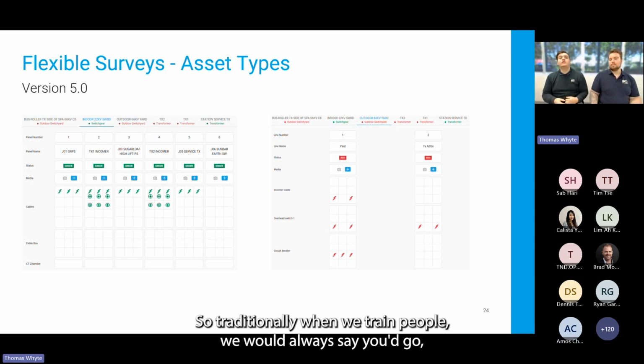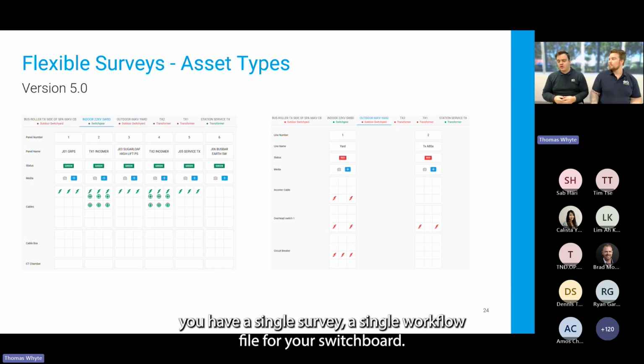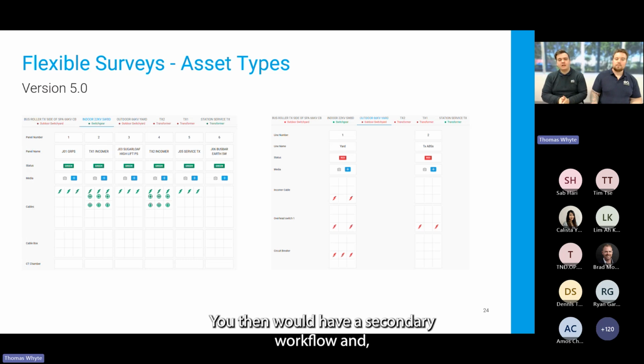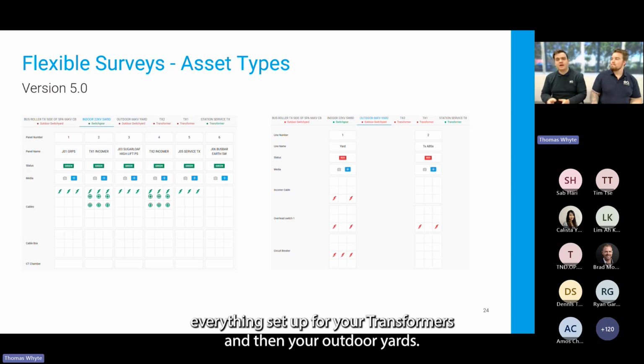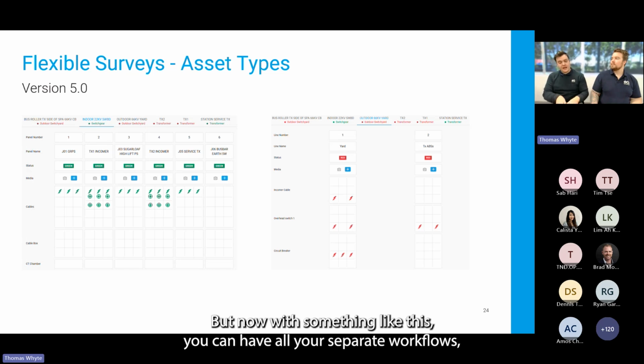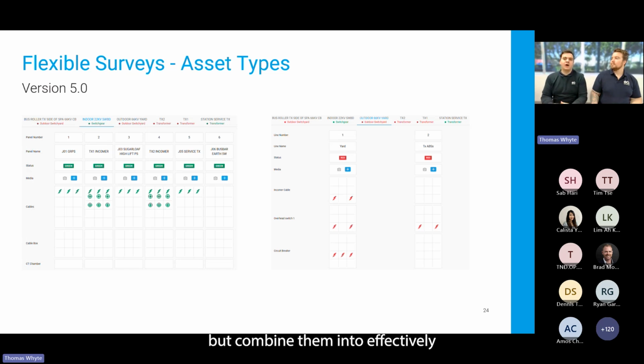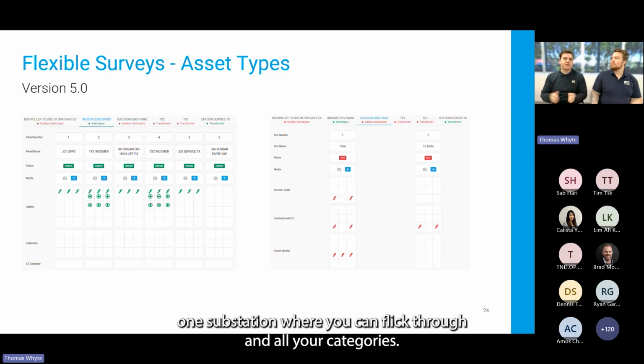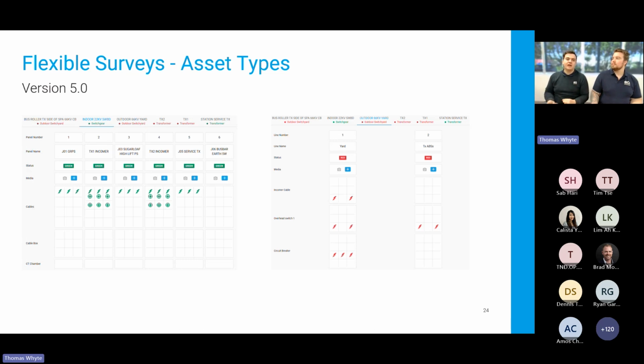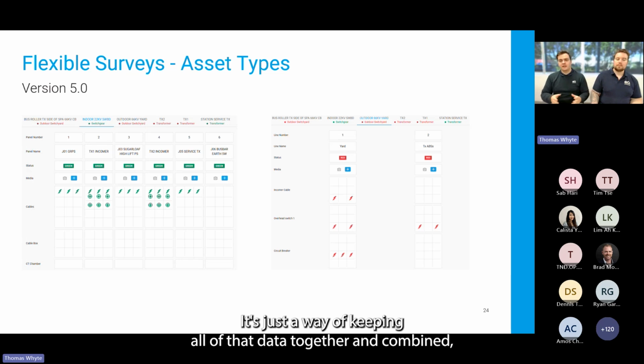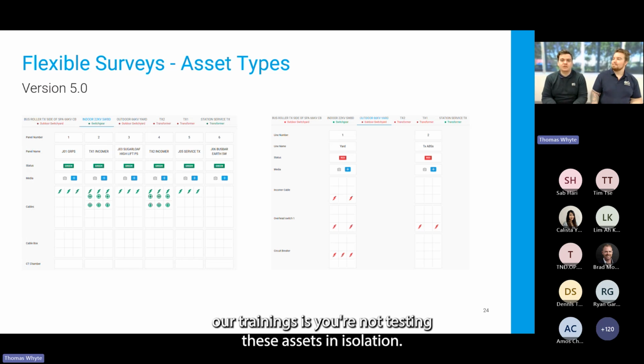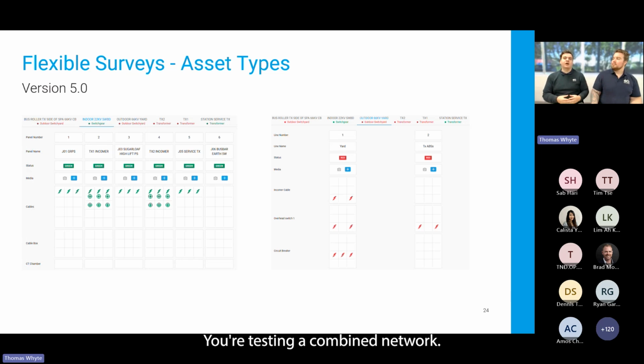Traditionally, when we trained people, we would always say you'd have a single survey, a single workflow file for your switchboard. You'd then have a secondary workflow set up for your transformers, and then your outdoor yards. But now, with something like this, you can have all your separate workflows but combine them into effectively one substation, where you can flick through all your categories. It's just a way of keeping all that data together and combined, because one of the things we constantly preach when doing our trainings is you're not testing these assets in isolation - you're testing a combined network.